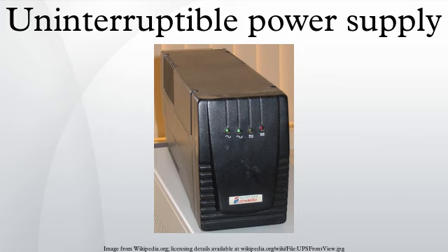The online UPS is ideal for environments where electrical isolation is necessary or for equipment that is very sensitive to power fluctuations. Although once previously reserved for very large installations of 10 kW or more, advances in technology have now permitted it to be available as a common consumer device, supplying 500 W or less. The initial cost of the online UPS may be higher, but its total cost of ownership is generally lower due to longer battery life. The online UPS may be necessary when the power environment is noisy, when utility power sags, outages and other anomalies are frequent, when protection of sensitive IT equipment loads is required, or when operation from an extended run backup generator is necessary.